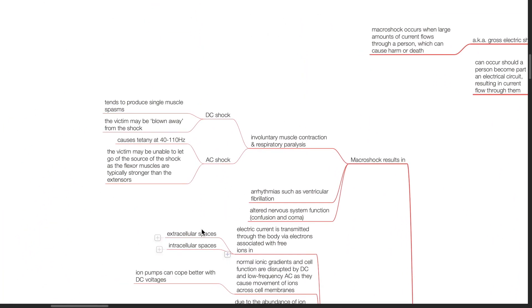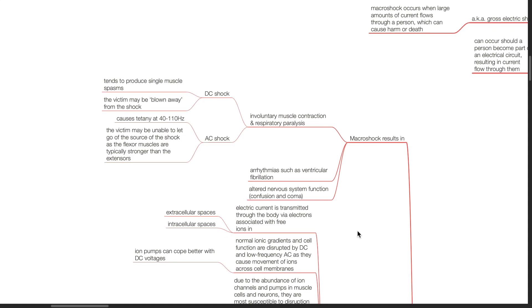Macroshock results in involuntary muscle contraction and respiratory paralysis. For DC shock, these tend to produce single muscle spasms. The victim may be blown away from the shock. For AC shock, they tend to cause tetany at 40 to 110 Hz. The victim may be unable to let go of the source of shock, as the flexor muscles are typically stronger than the extensors. Arrhythmias may occur such as ventricular fibrillation. Altered nervous system function may result in confusion and coma.